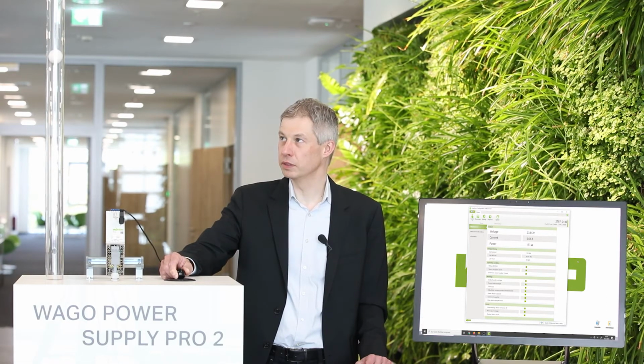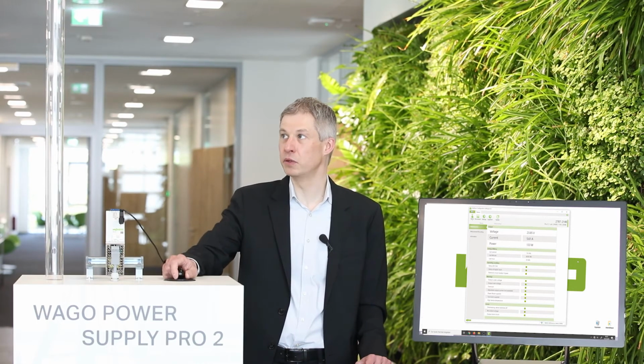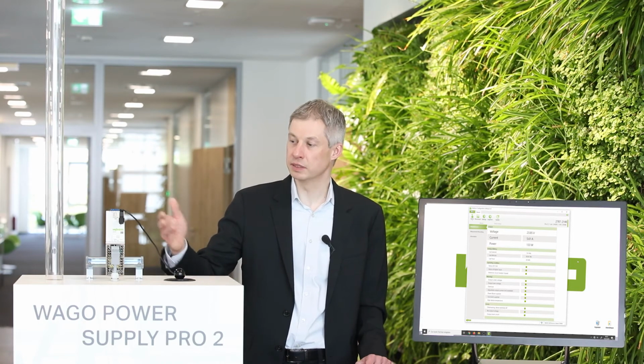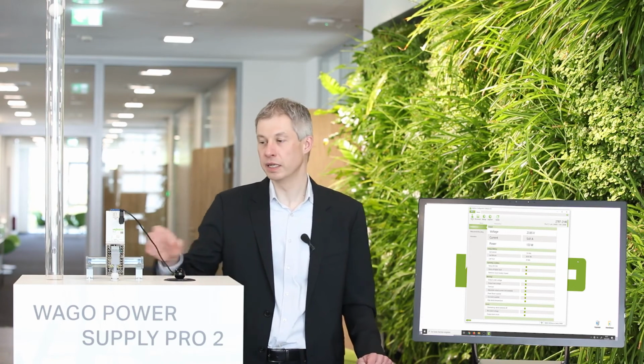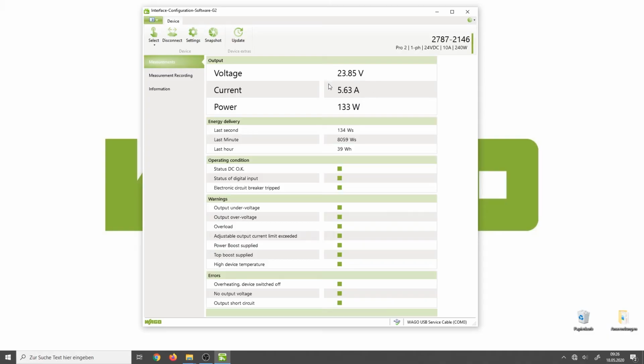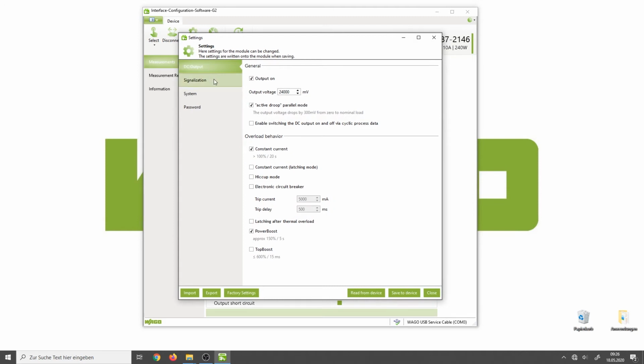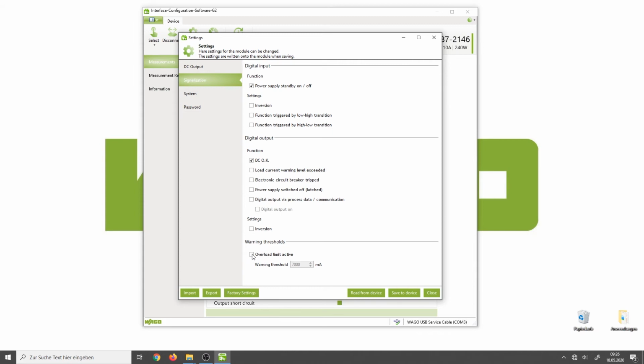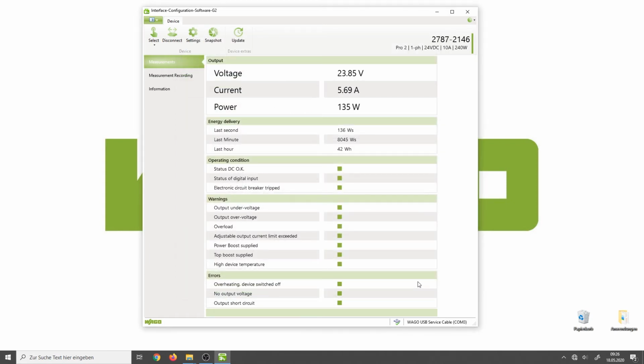Depending on the airflow, we have different currents where the fan is supplied, and via the interface cable we see this on the software here. If we want to have a special setting, for instance, to have a warning message in case the output current is too high, then we can set here overload limit, and here it is set to 7 amps. We say save to the device, close that again, and this warning message is displayed here under the adjustable output current limit exceeded.